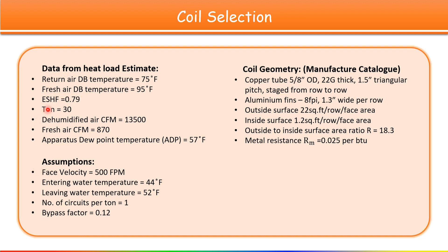We also need the effective sensible heat factor (ESHF) value. In our case, we are assuming the return air dry bulb temperature is 75°F, fresh air dry bulb temperature is 95°F, effective sensible heat factor is 0.79, and tons of refrigeration is 30. Dehumidify CFM is 13,500, fresh air CFM is 870, and apparatus dew point temperature is 57°F.